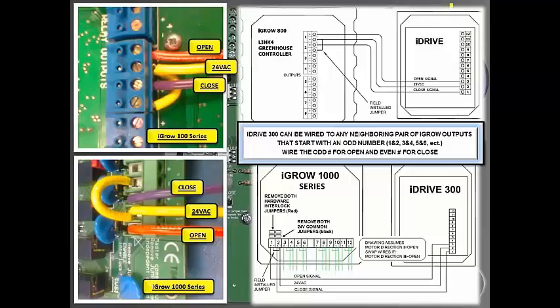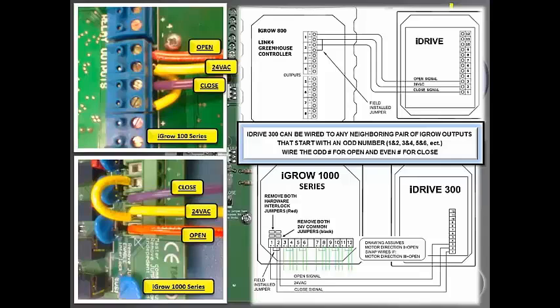The iDrive can be wired to any neighboring pair of iGROW outputs that start with an odd number: 1, 2, 3, 4, 5, 6, etc. Positive 1 would be for the open signal, positive 2 would be for the closed signal, and 24 volts would go to the negative of both outputs to provide power throughout the two channels.